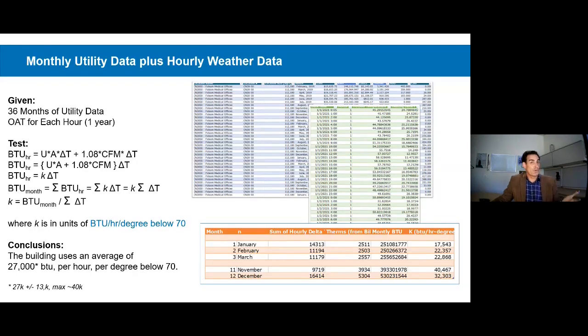We can take this further. When we do a heating load calculation, there are 2 components. There's an envelope component, we call that UA delta T, and then there's a ventilation component, we call that 1.08 CFM delta T. If we combine those, we can get a single scalar factor that's related to delta T. So it would be a UA plus 1.08 CFM all multiplied by delta T.